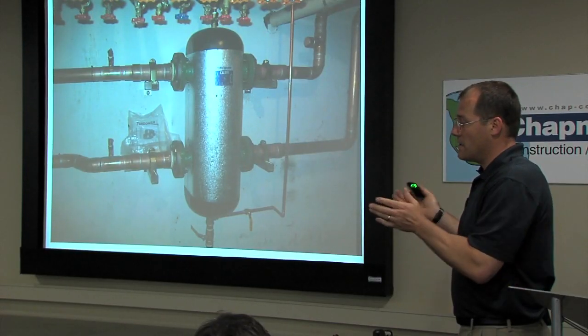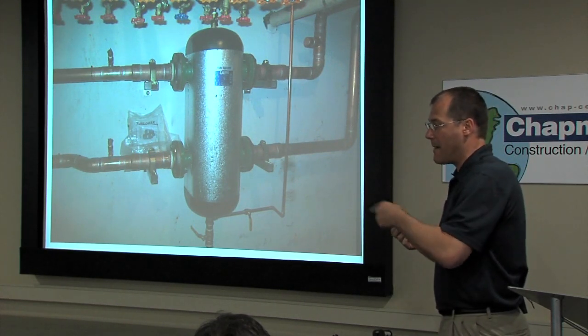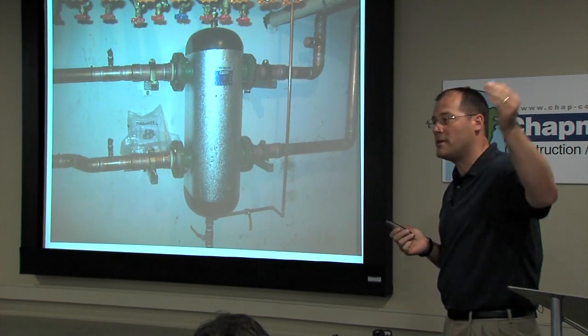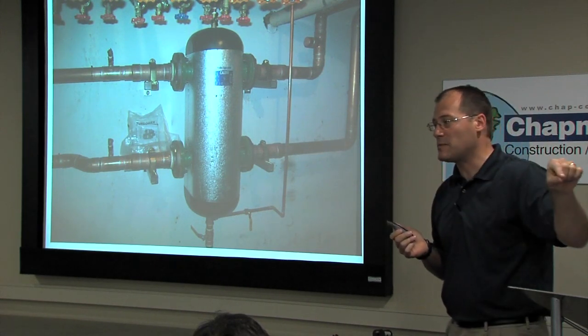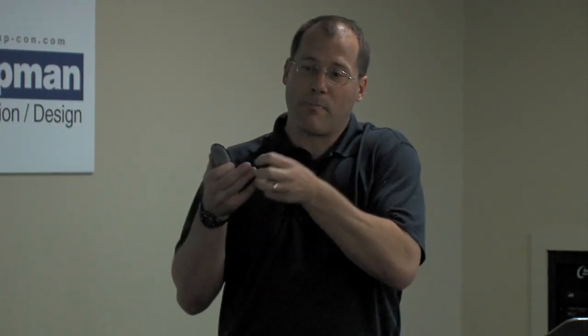We do that now with a very small volume, we might have 2, 3, 4, 5 gallons of water in the boiler at the same amount of BTUs going in. So flow is critical. There's a minimum flow requirement on all this new technology. Quite often, let's take a boiler that has a 20 gallons a minute flow requirement. So it has to be happening. But you've got a system with 30 zone valves and some 3/4 baseboard that might only have 1 gallon a minute per zone or 2 gallons a minute. We need to separate or decouple that boiler from the building loop.